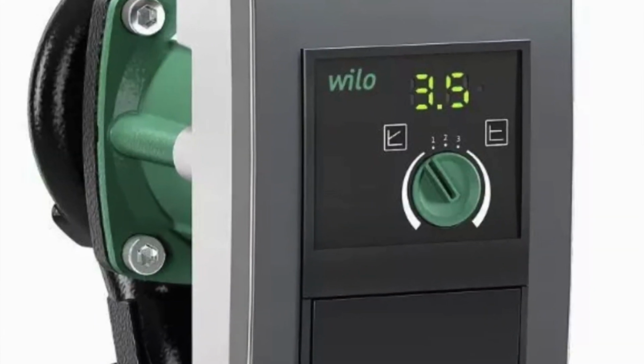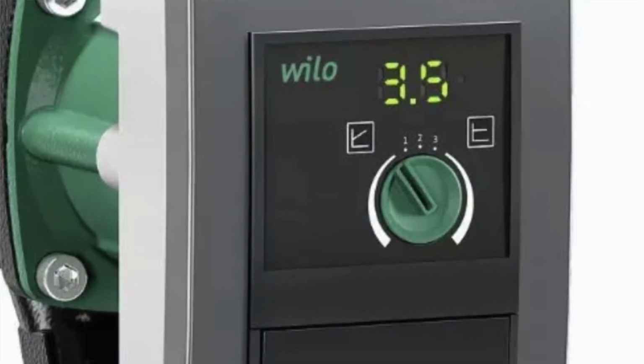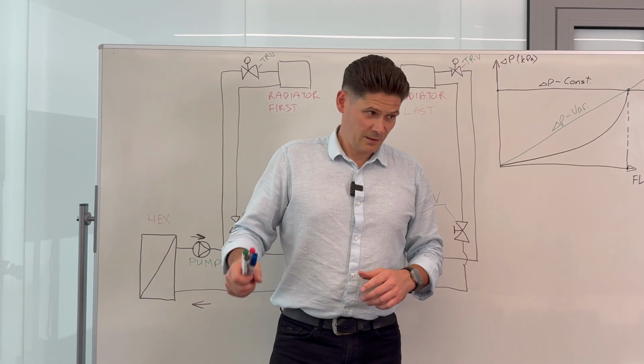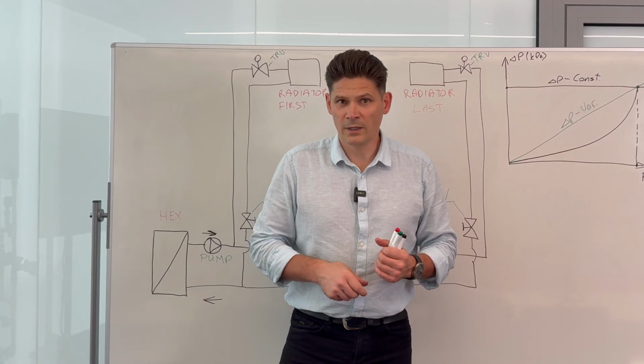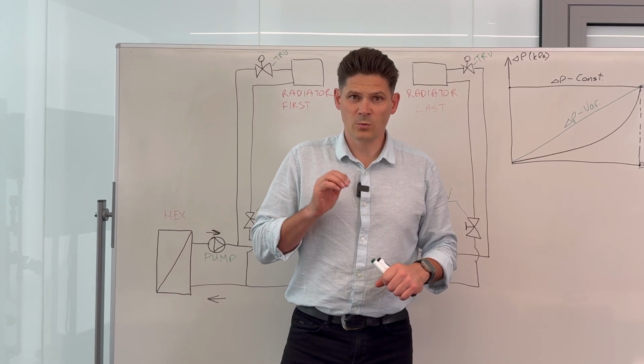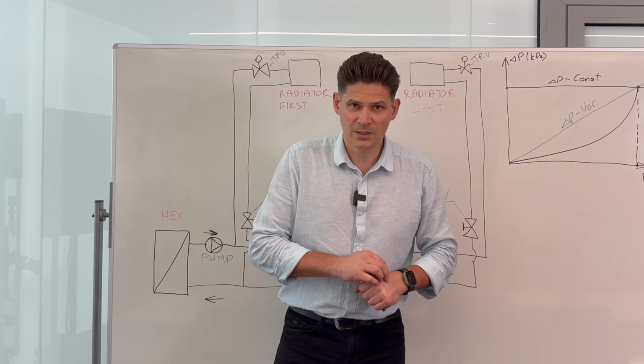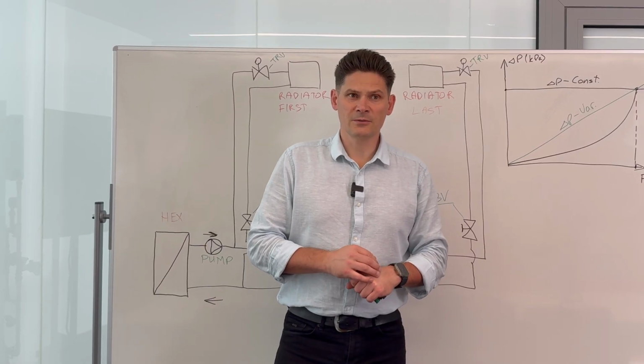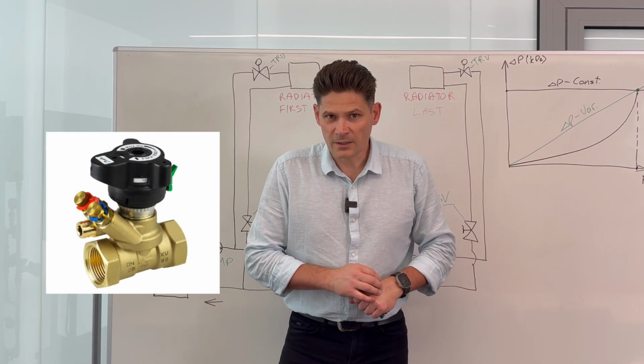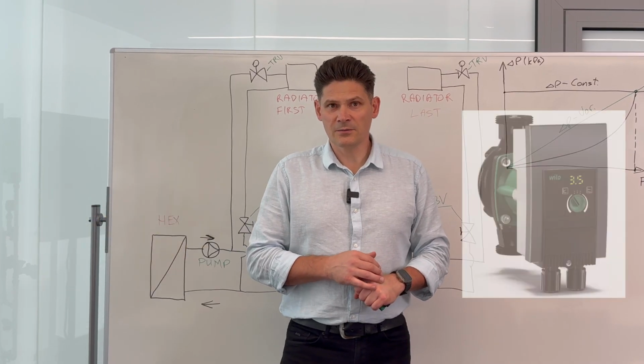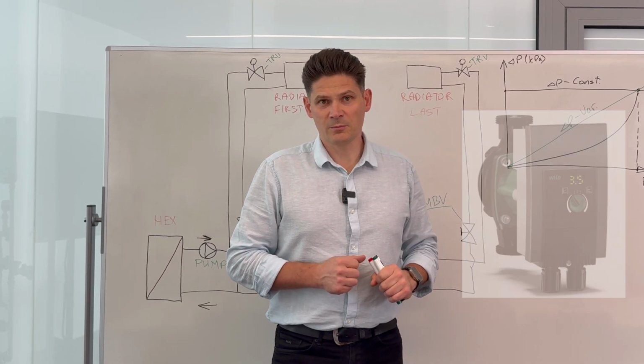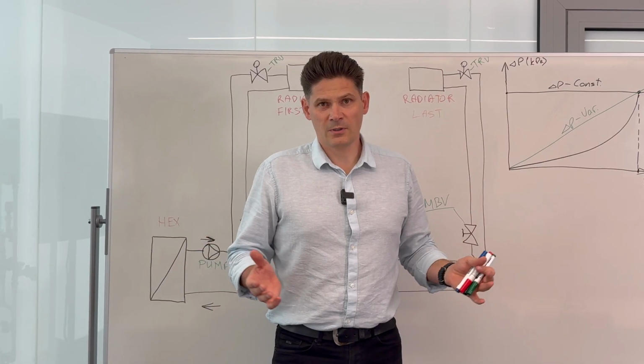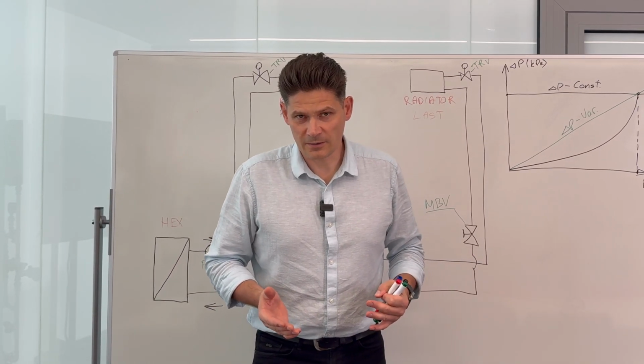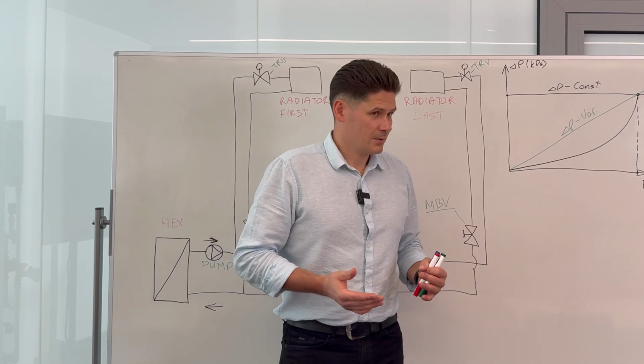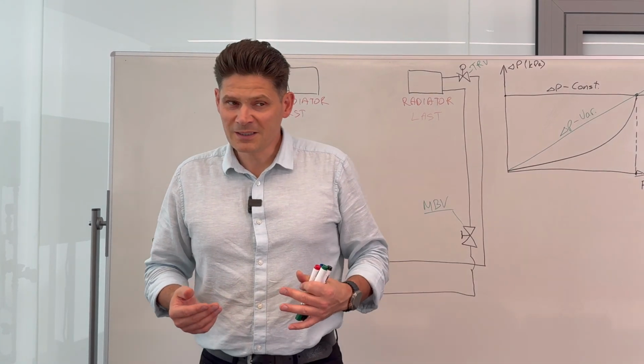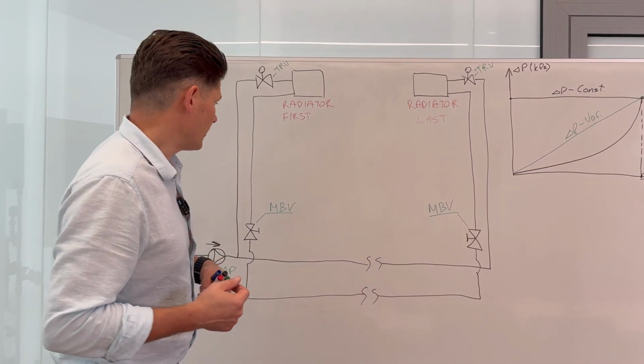But still, somehow, we still use manual balancing valves, and in a few minutes I will prove why it is wrong, and why you are having problems with under balancing, with flow shortage, if you're using manual balancing valves with modern circulation pumps. Actually, in European Union, you are not allowed to use any other circulation pumps. So why are you still using manual balancing valves? This is a big question for me.